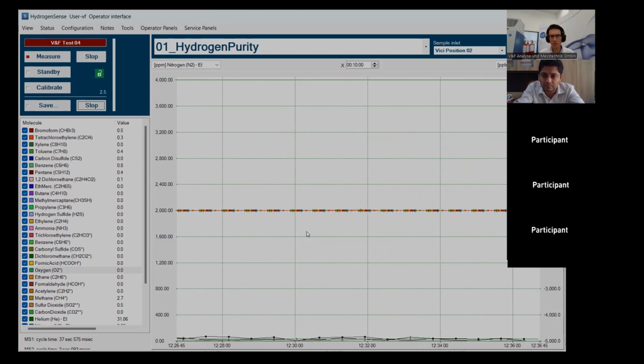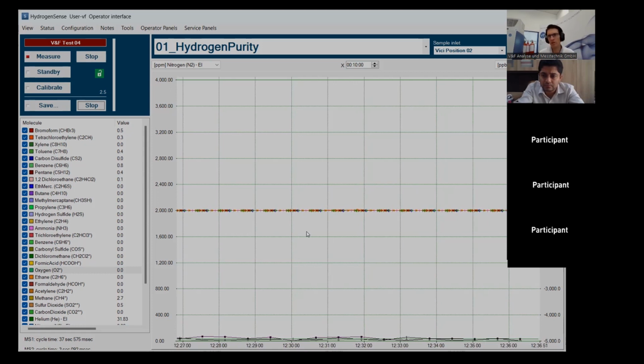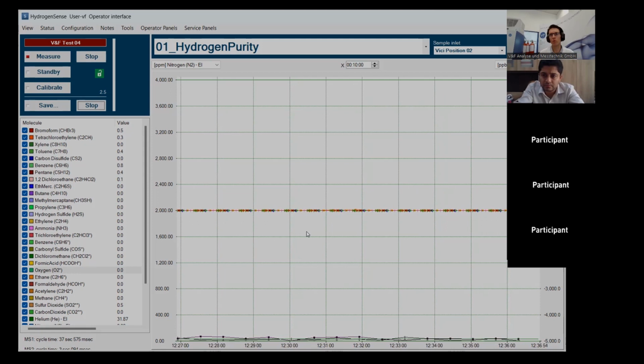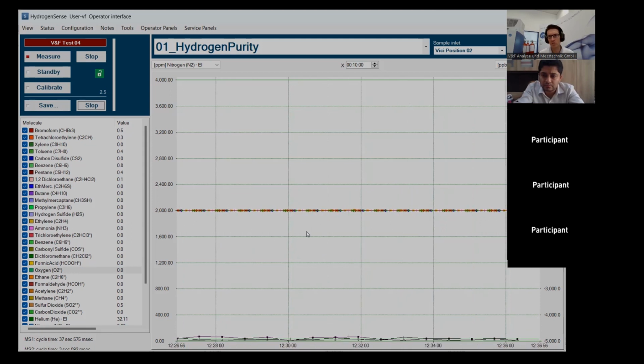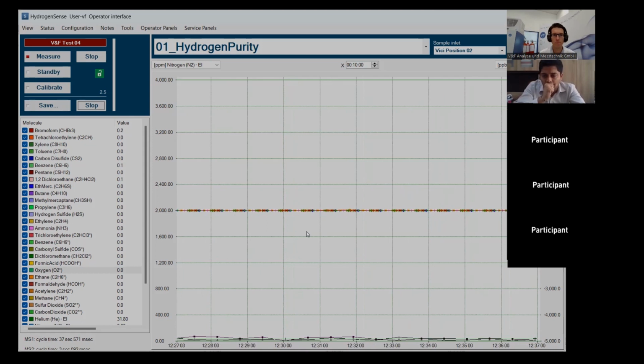If you know you won't use the instrument for 3 or 4 days, then you can stop the supply and put it into standby. The only thing you need to remember is that before you want to do the analysis, you should give the instrument about 24 hours on the hydrogen gas in order for everything to be saturated out. Okay, thank you.